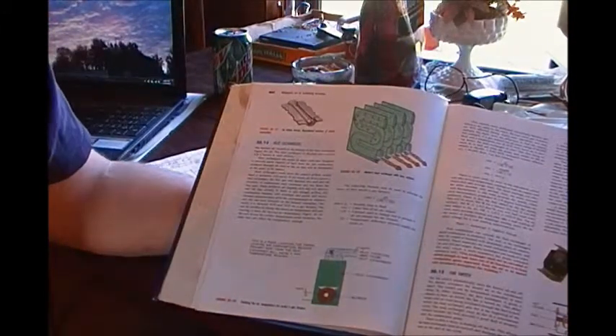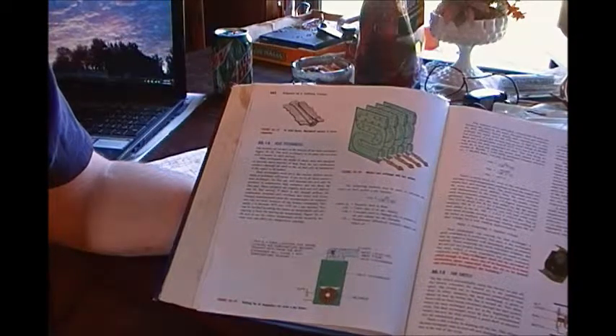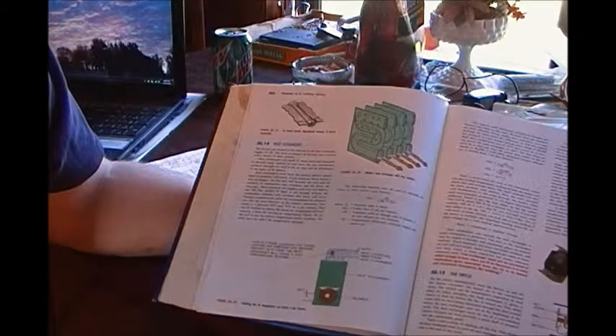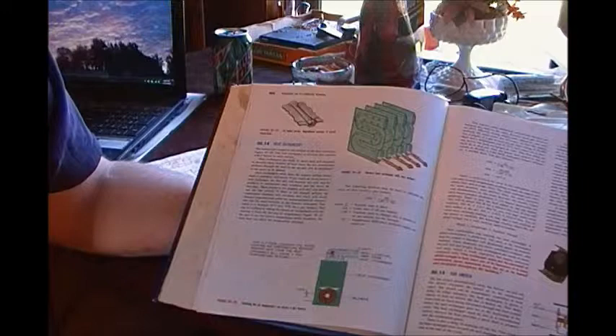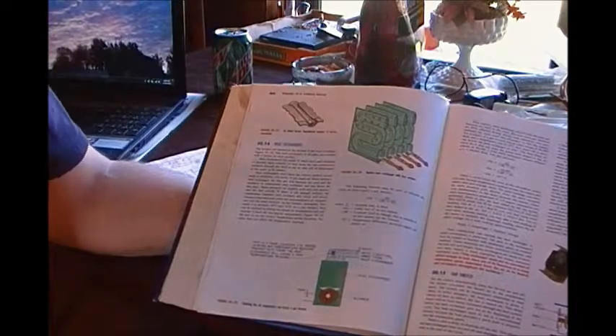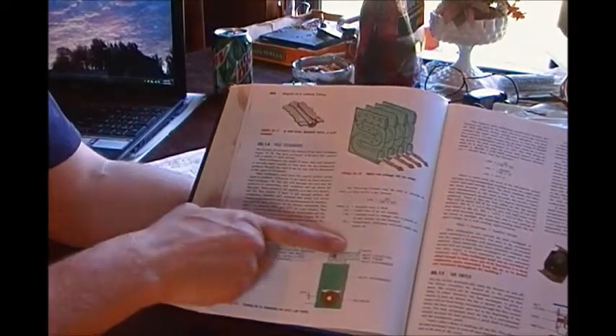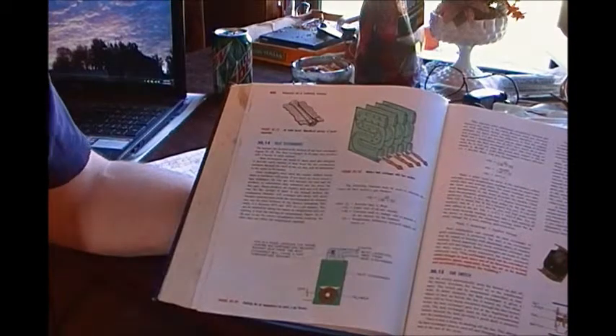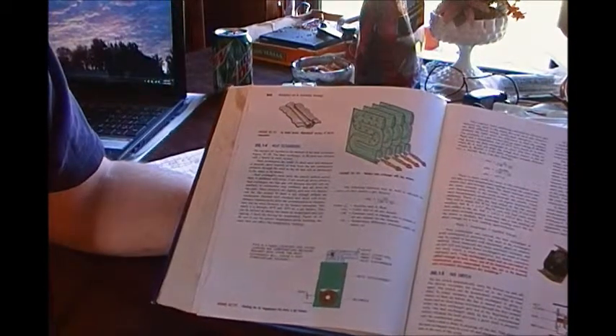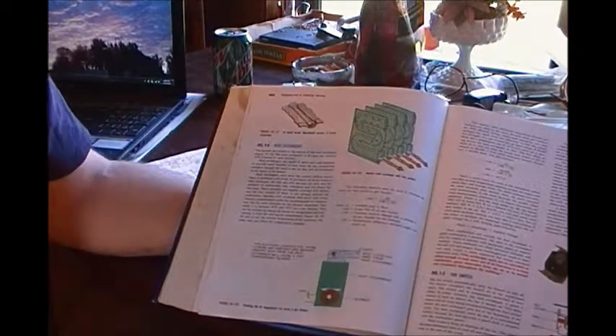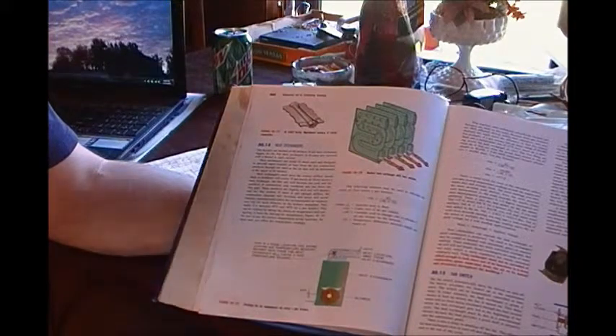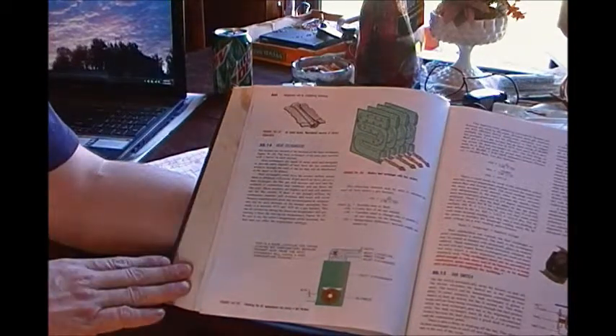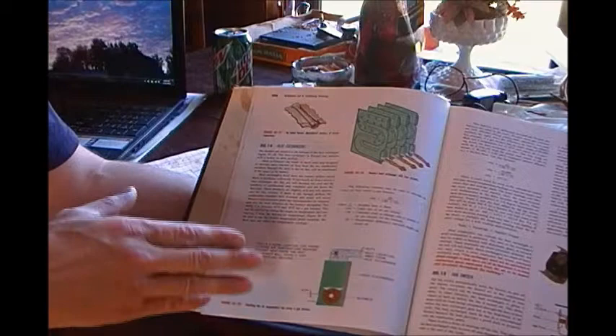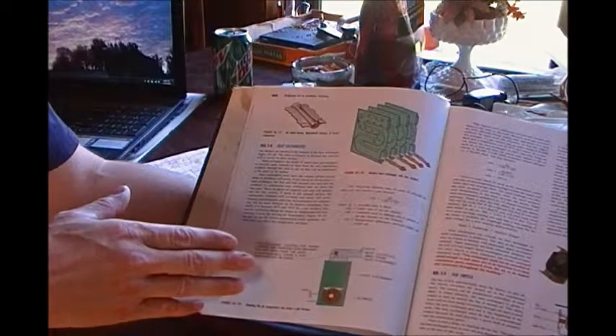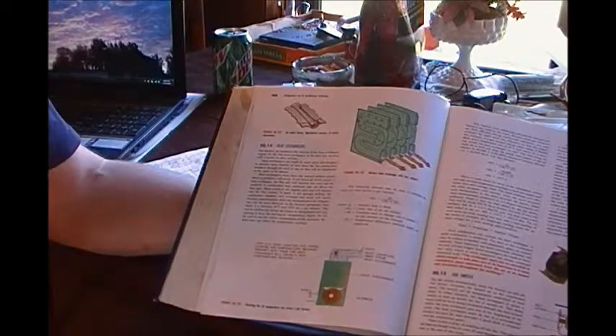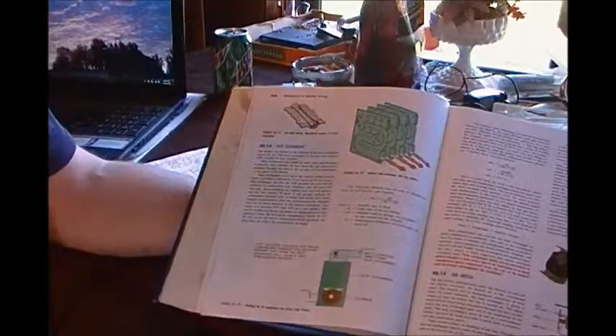And so if you're getting 70 and you're blowing out 170, then it's too high. You need to increase the amount of flow of air going across that coil. If you put your thermometer here and you're reading 70 and you're getting 130 out the top, guess what? Then you're right within your 40 to 70 degree difference, and it's fine and it's balanced perfect. So there you go. Not only do you want to worry about your 3.5 gas pressure, but you also want to know your RPMs and airflow across that coil. And that's how you properly balance a system.